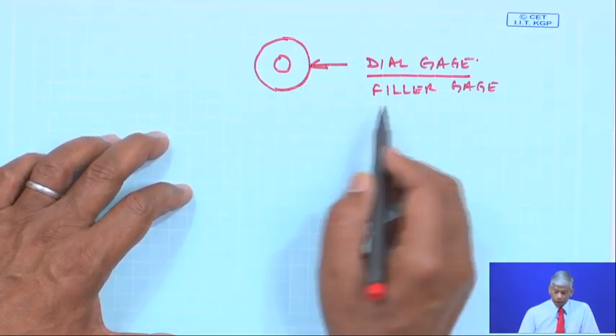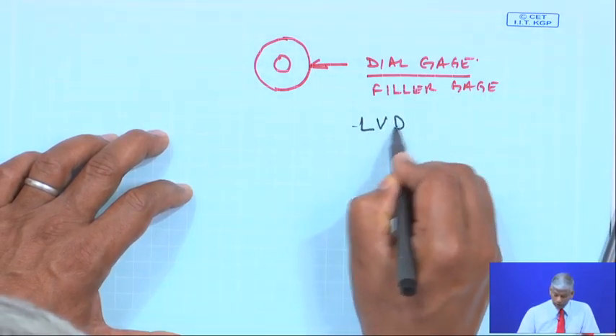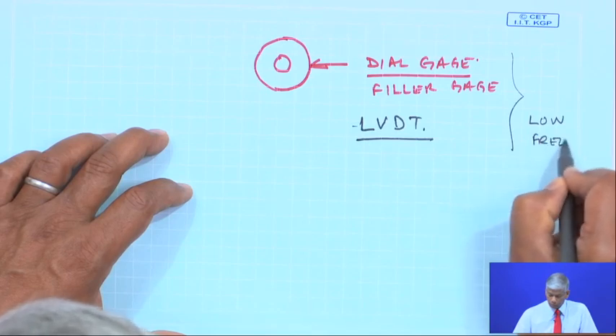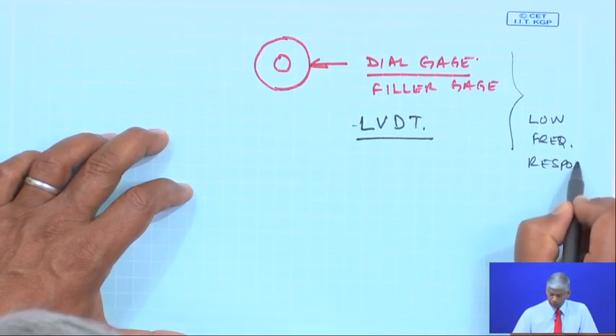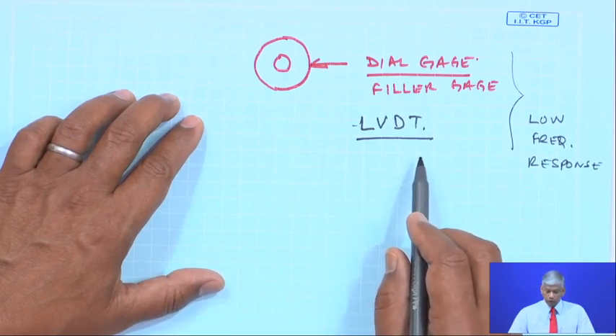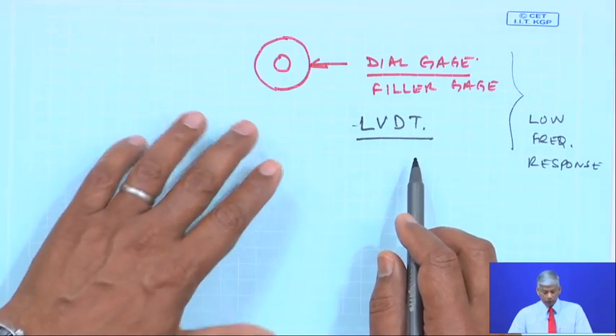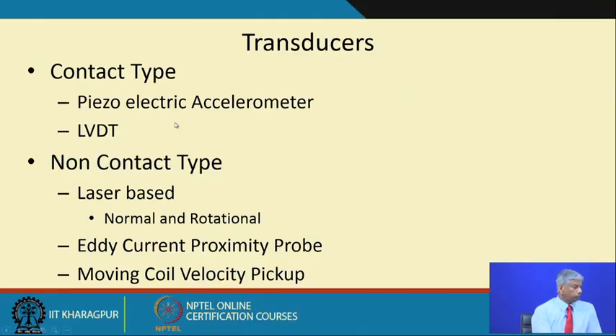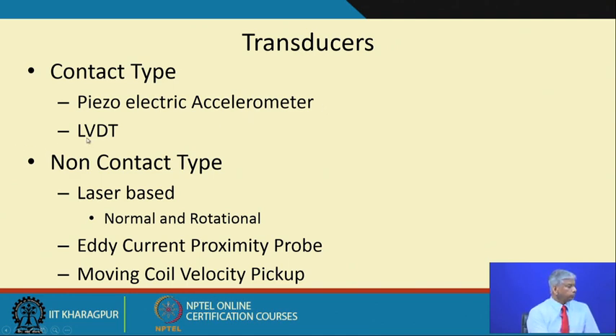A mechanical device like an LVDT is another option, but these devices have a low frequency response. Since the phenomena itself is slowly moving, I can use such transducers — be it a dial gauge or an LVDT — to measure displacement. To summarize contact-type transducers: piezoelectric accelerometers measure acceleration; dividing by ω gives velocity if necessary; and for displacement, an LVDT can be used.